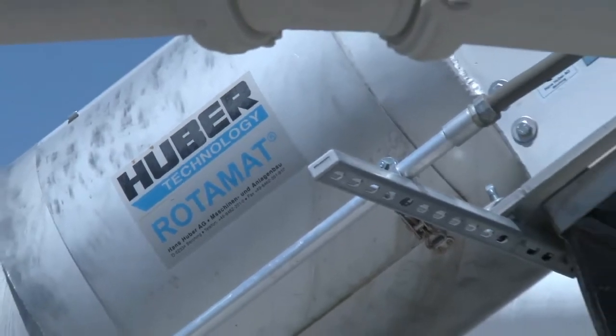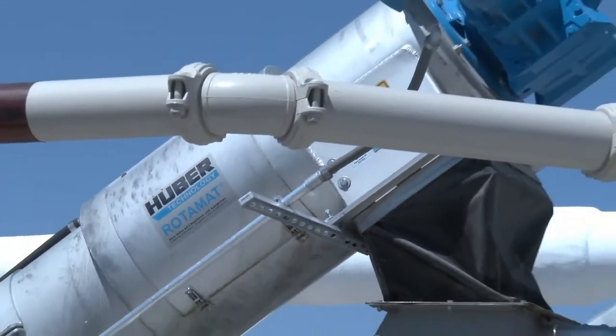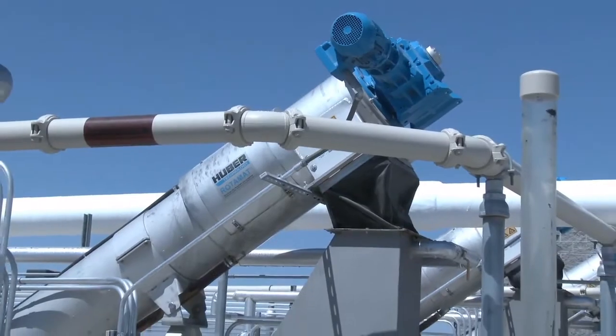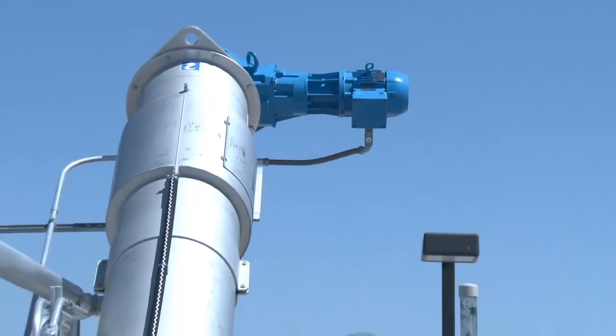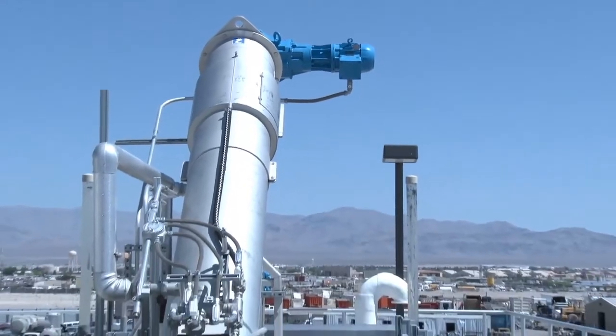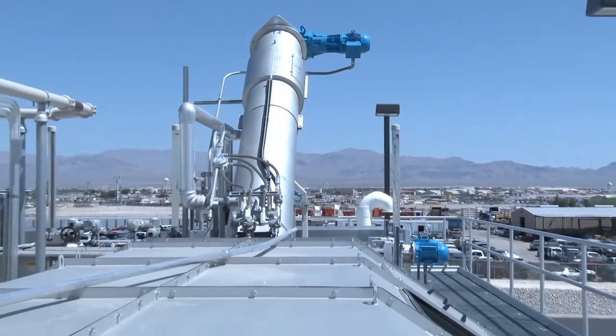What we have installed here at the North Las Vegas plant is a Rotamat RPPS 2600 fine screen — a 2 millimeter screen. At the time it was put in, it was one of the largest in North America. The fine screens are here to screen out anything that might get into the bioreactor that could possibly be introduced into the membranes.